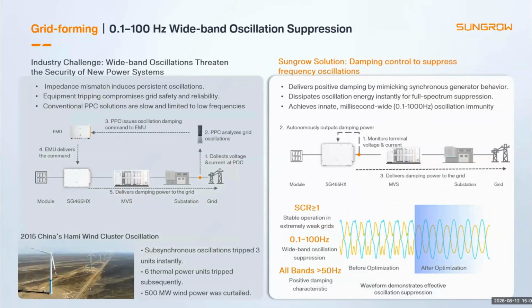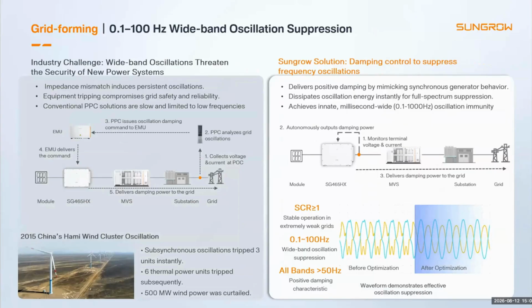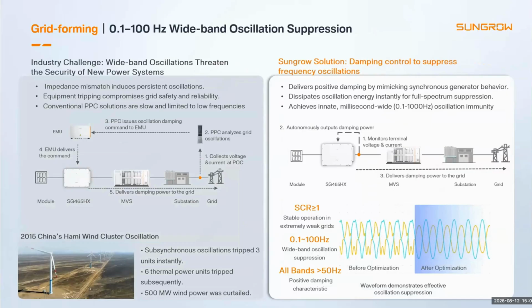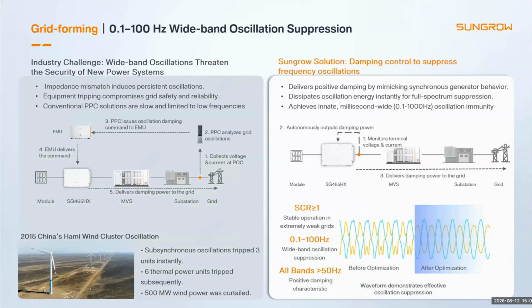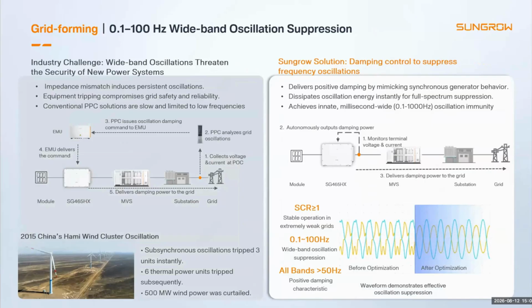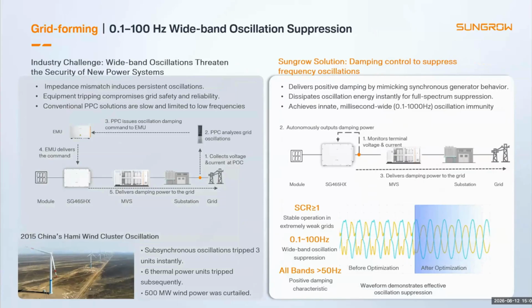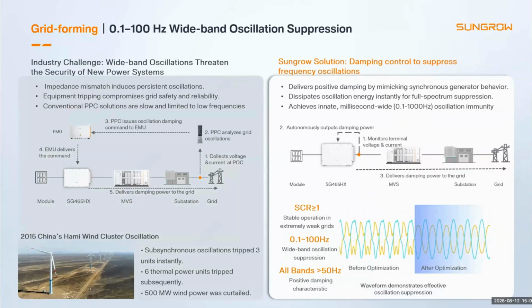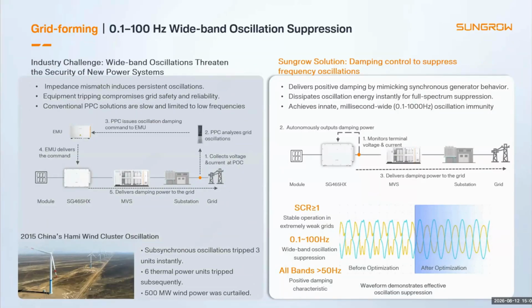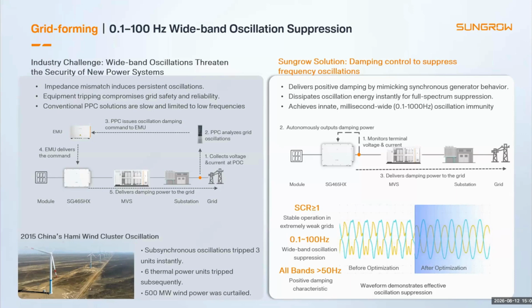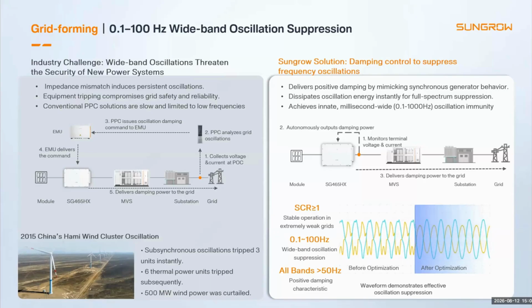Weak grids can also suffer from wideband oscillation caused by interaction between inverter impedance and grid impedance. Traditional plant level control is relatively slow, but our solution provides active damping directly at inverter level, helping suppress oscillation over a wide frequency range. The objective is to maintain stable operation even in very weak or highly renewable grids.